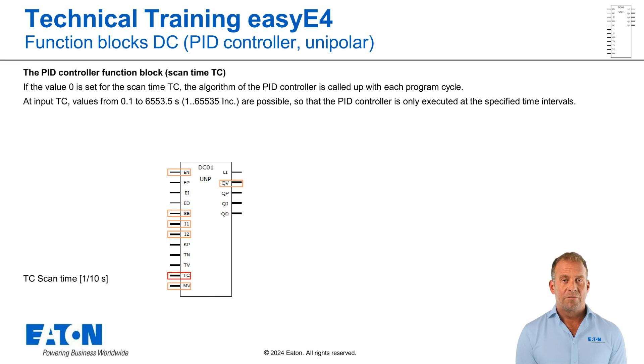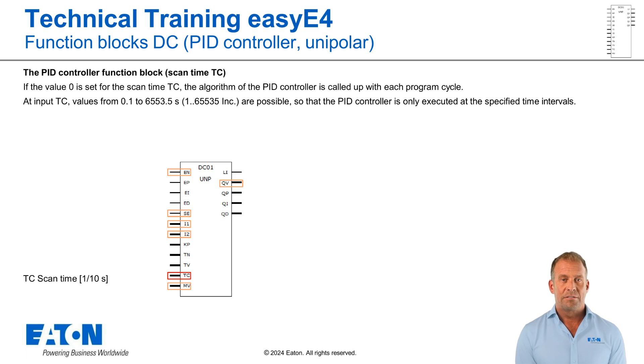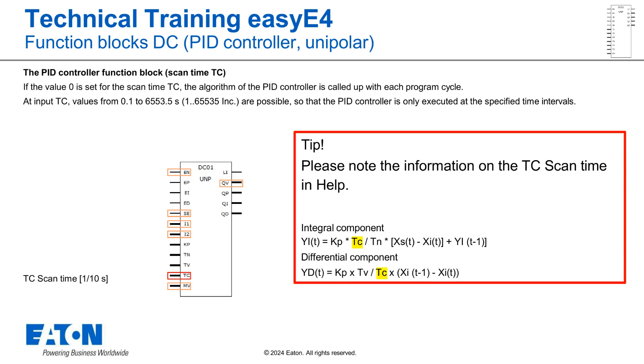Another analogue input of the DC module is the one for the scan time TC. If TC is set to 0, the controller is called up and processed with every program cycle. You can transfer values between 1 and 65535, corresponding to 0.1 to 6553.5 seconds, to the function. As a result, the controller is only executed at the specified intervals. The scan time is included in the calculations of the I and D components of the algorithm — please refer to the formula in Help.